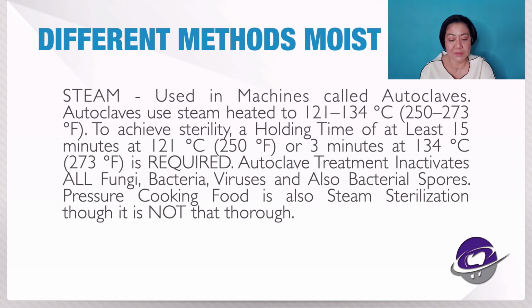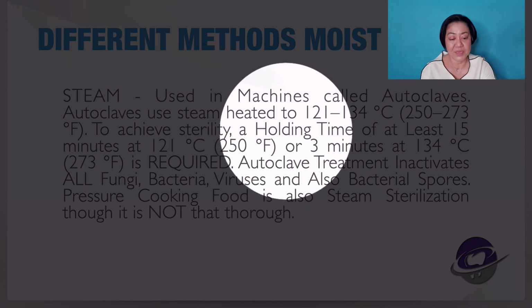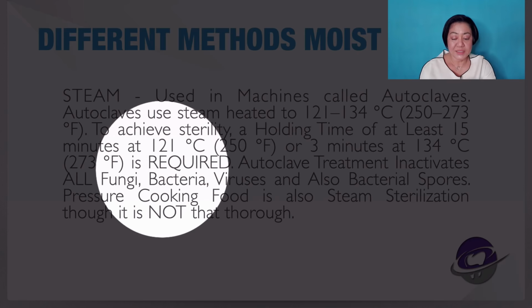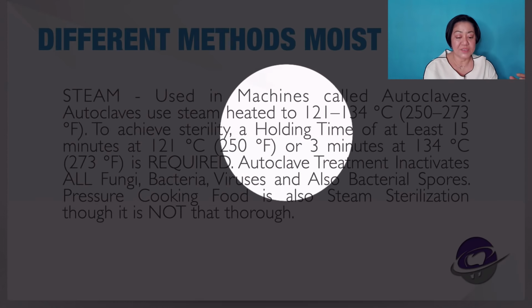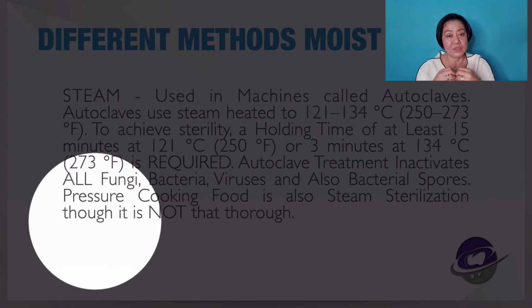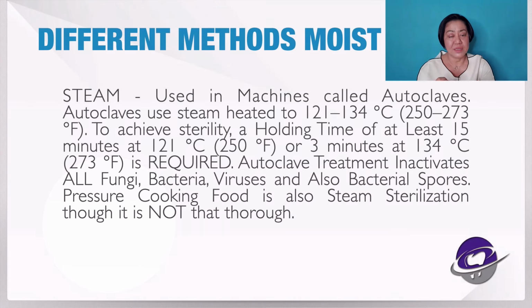Okay, so the steam sterilization, which is what I'm going to tackle more, because this is the most important part right now. Steam sterilization requires direct contact between the saturated steam and every surface of the instrument. So it means the autoclave or steam sterilization will work well only if there's direct contact to the instrument you are trying to autoclave.